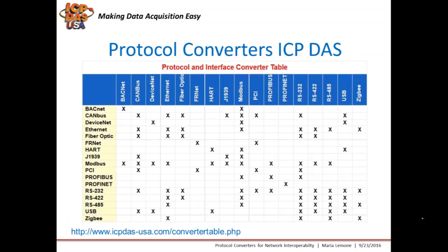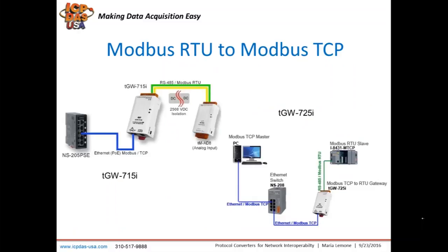Modbus is the de facto standard in industrial communication, as it has an open standard specification and easy implementation. There are a lot of code examples available on the internet for developing custom software. Most SCADA software, like Indusoft and KingView, come with Modbus drivers. Modbus's simple master-slave protocol technique is straightforward and doesn't require a special token to establish communication. A cost savings point is Modbus doesn't require special cabling, as it can be transmitted on a simple twisted pair insulated copper wire for Modbus RTU and standard Category 5 Ethernet cables for Modbus TCP.